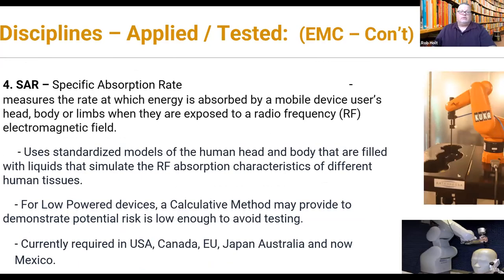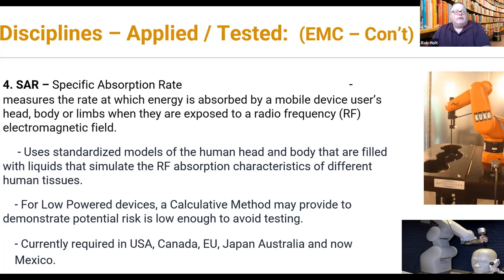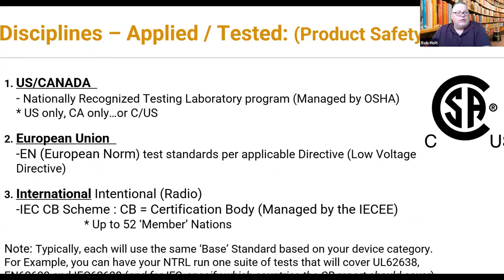Most RF devices will require SAR — specific absorption rate — which is the ability of the device to induce radiation into the tissues of the human user. It's required for all cell phones, laptops, and devices used within a certain proximity. Testing is typically done by the head or by the hip. If your device is low power, sometimes you can use a calculated method and skip the actual testing. This is something you need to be planning for when making an RF product.